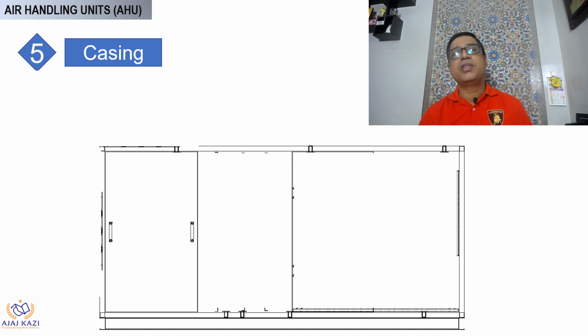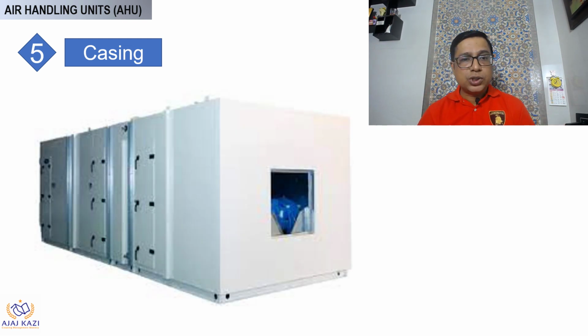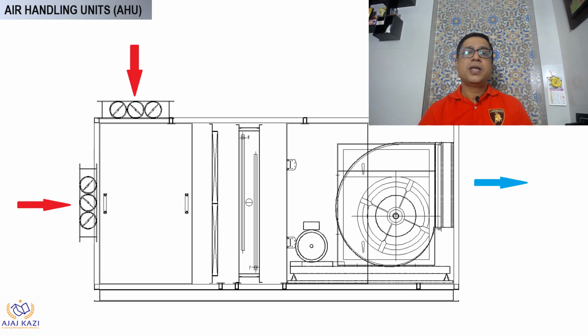And everything is encased in a casing. The casing is generally made of PUF, 48 kg density generally, though it can vary from application to application. And this casing will have doors for accessing the blower, the coil, and the filters. All these doors will be placed strategically for proper access. This is how the casing looks in real, and this is how the AHU gets completed.